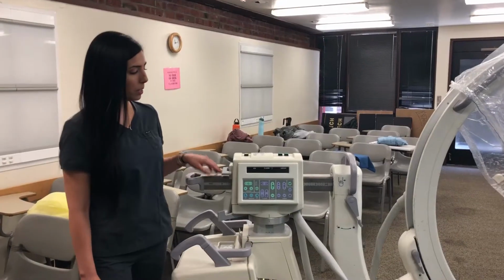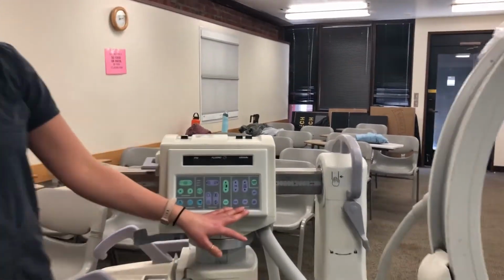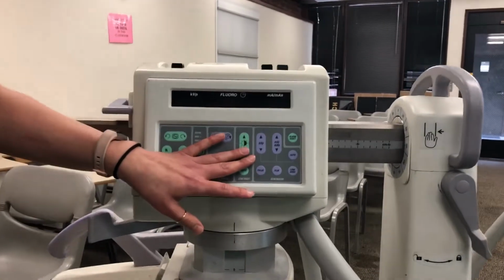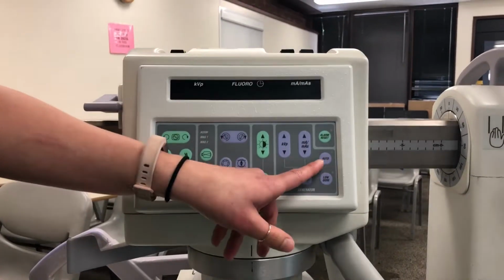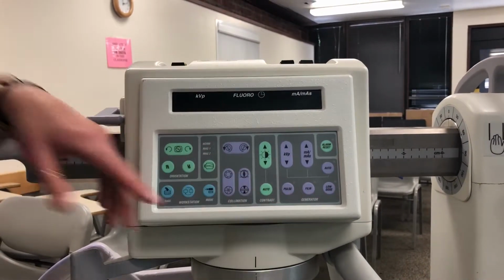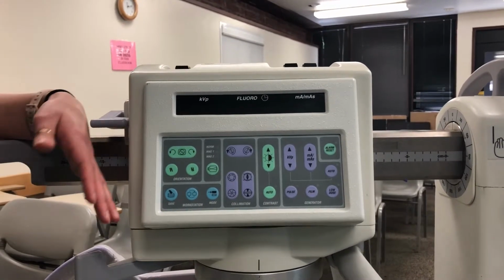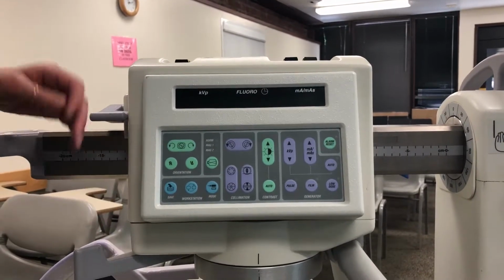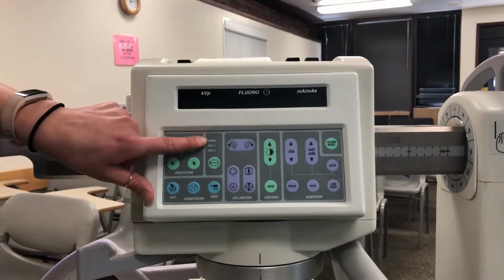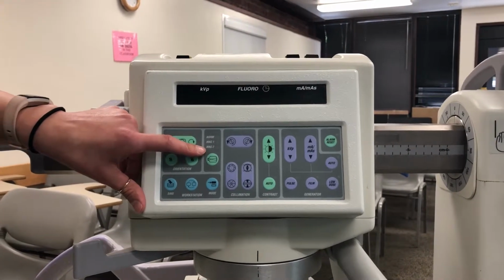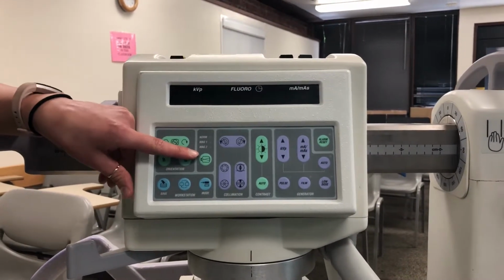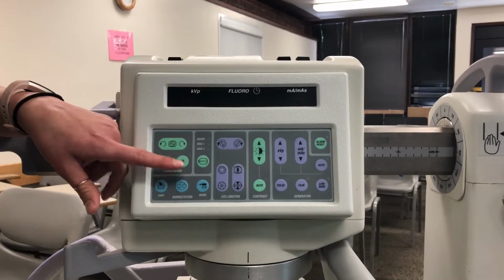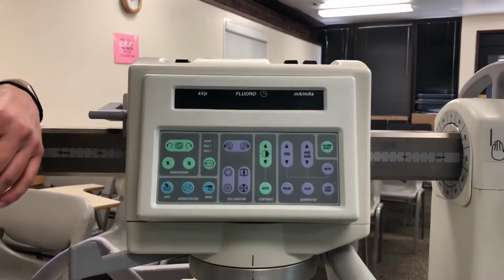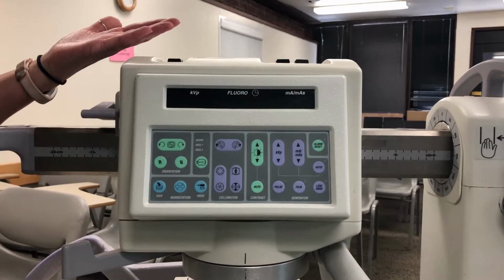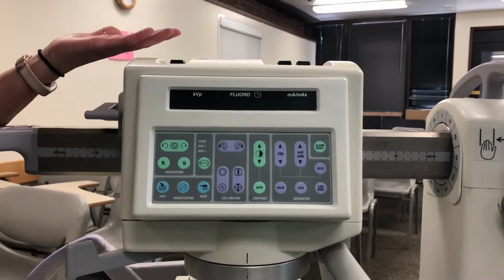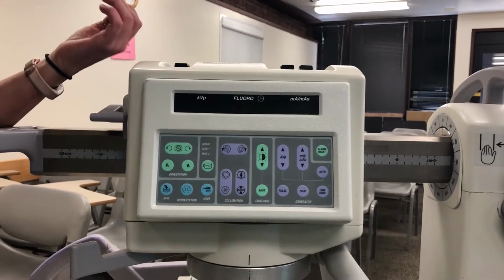So some other buttons that you'll use when setting up are regarding your technique. Typically you start in auto and low dose. If you have a very large patient or you're doing a spine case, the doctor might ask you to go into mag mode. And here are your options here. On this machine, you have two options for mag mode. It's important when you're done taking images, once you're going back in to retake images, to ask them if they still want mag mode, or just remind them throughout the exam.